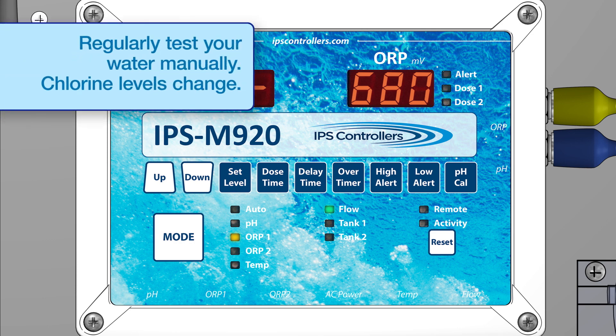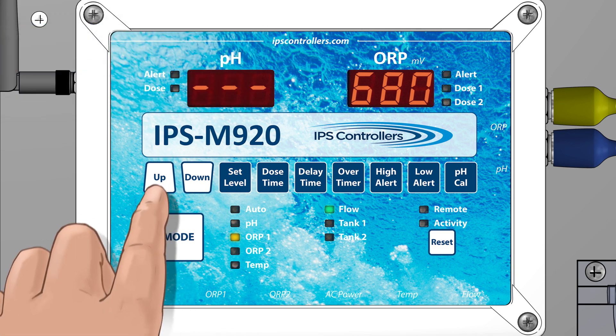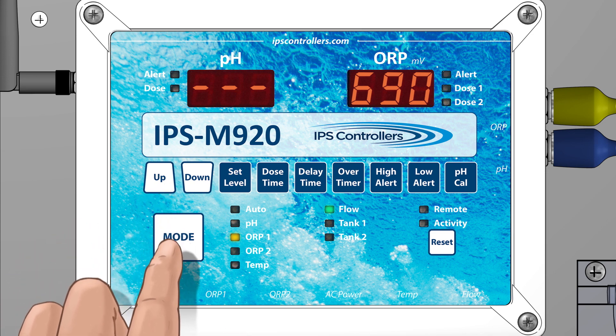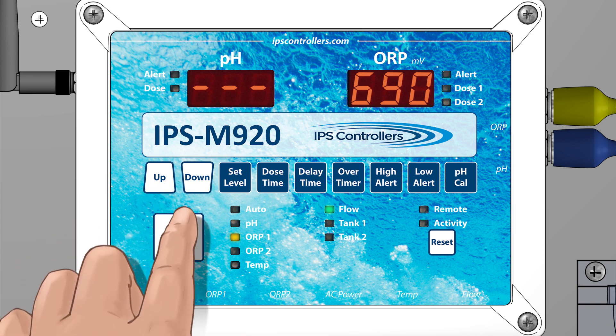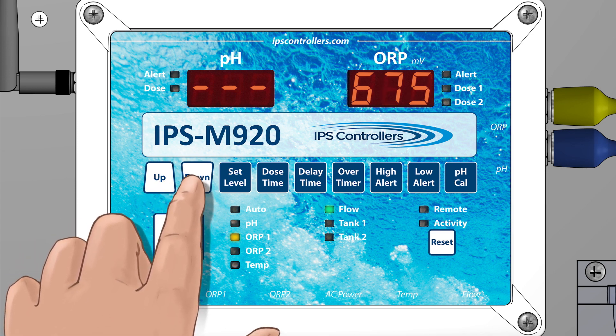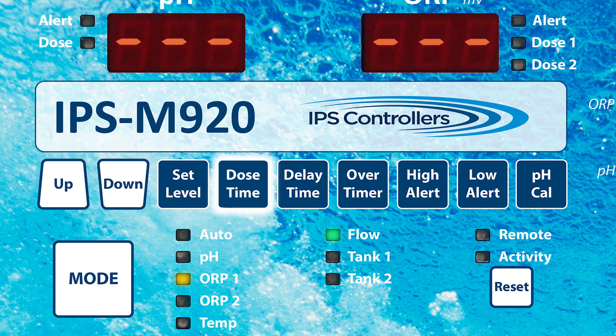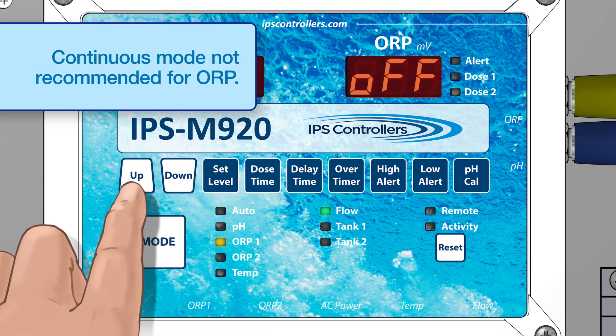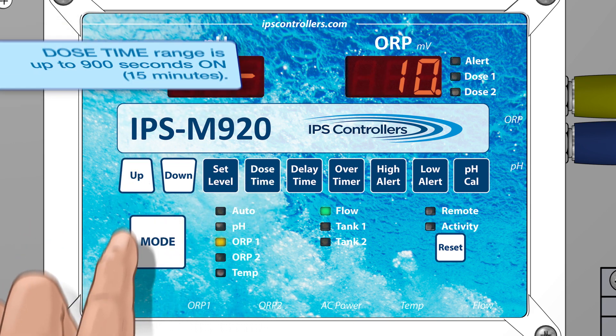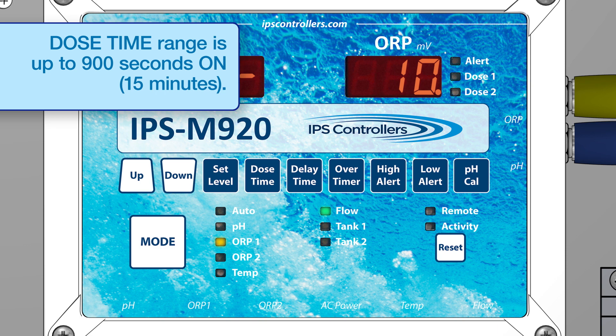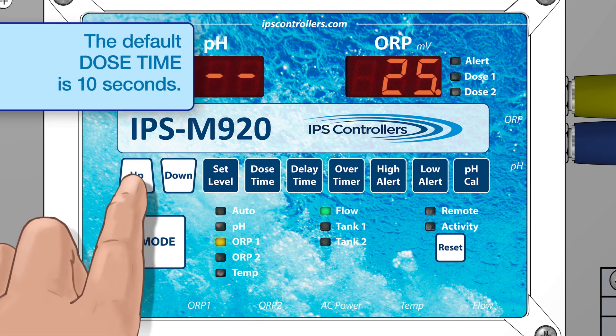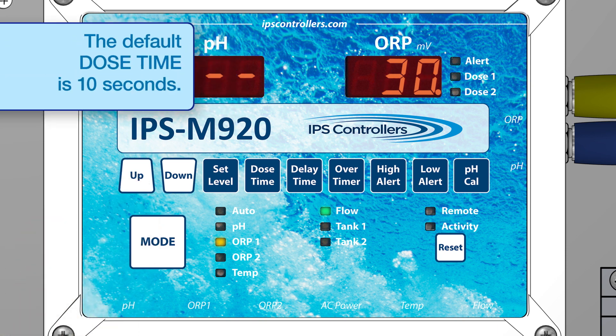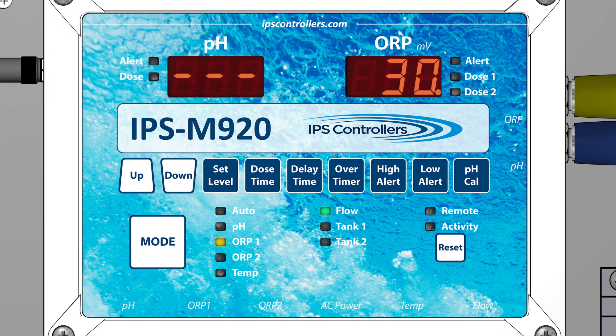If a future manual water test shows a PPM reading that is lower than desired, increase the ORP set level by 5 to 10 millivolts. If the ORP reading is too high, lower the set level. Press the Dose Time button and using the Up or Down buttons, set the dose time to off, continuous, or timed up to 900 seconds on. To avoid overdosing, start with a lower dose time and adjust up to maintain the set level.